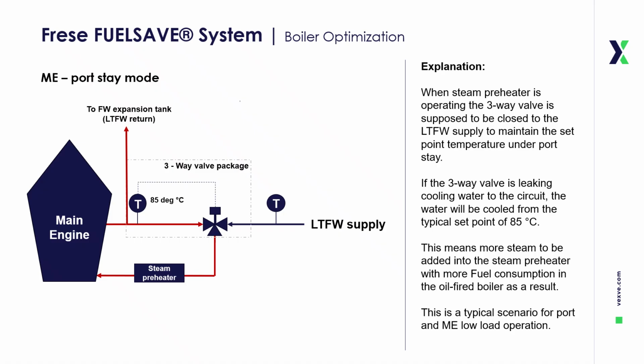The direct consequence is increased steam demand, which leads to higher fuel consumption in the oil-fired boiler. This scenario typically arises when the vessel is in port or during main engine low-load operation, conditions where preheating demand is highest. By applying low-leakage three-way valves as part of the Frese FUELSAVE system, this unnecessary cooling is eliminated. The system maintains stable water temperatures, minimizes steam usage, and significantly reduces boiler fuel consumption, improving both efficiency and operating costs.